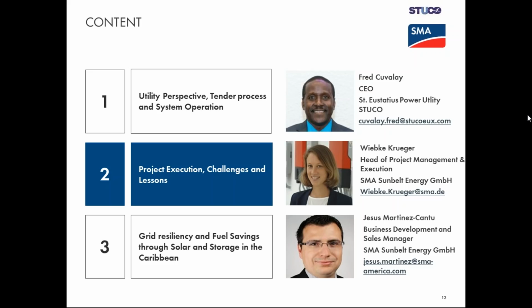And I would add one more point. I was not surprised that most of the respondents were not caring so much for reactive power supply. On Stuco also, this was not a concern at all, because we already have 55% of our medium voltage lines on the ground, and they provide a significant capacitive load for the grid.